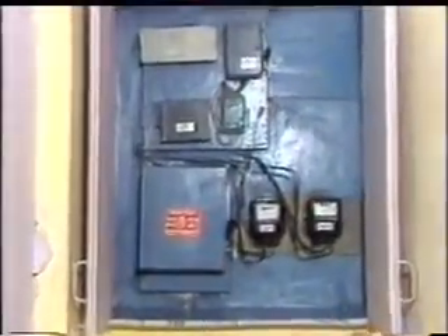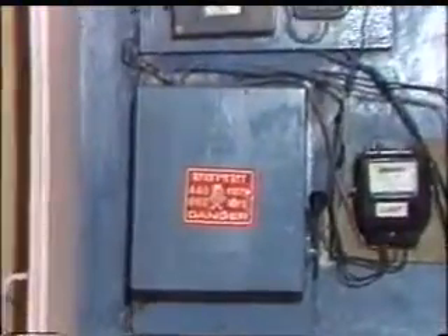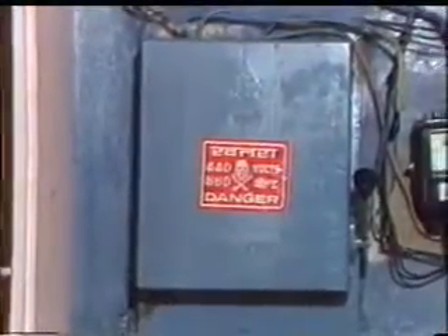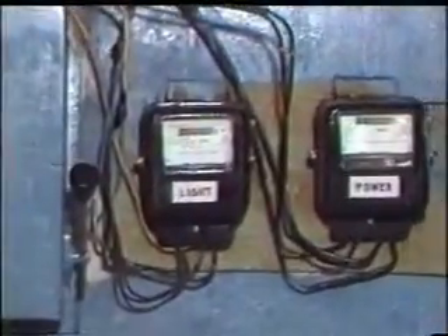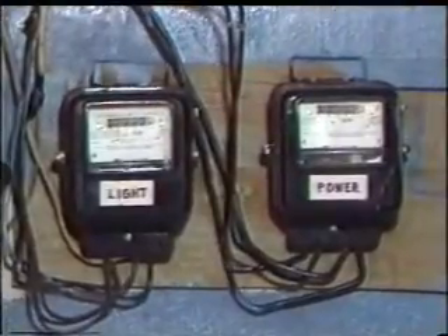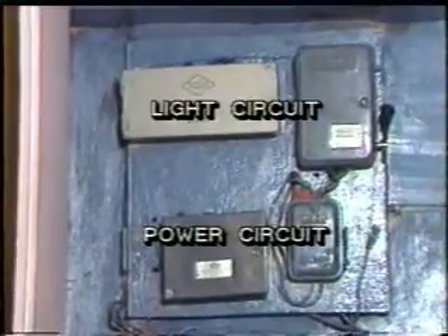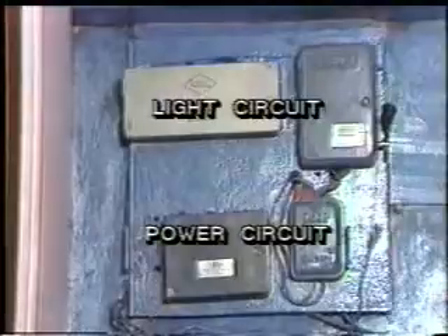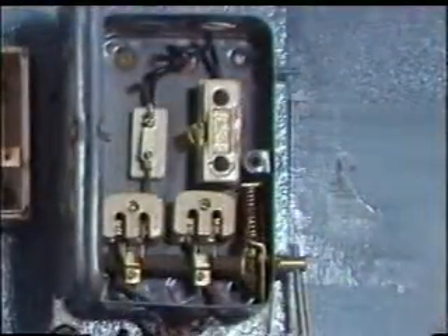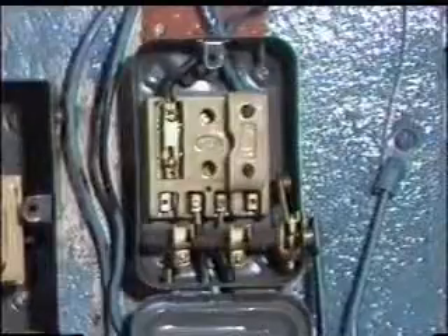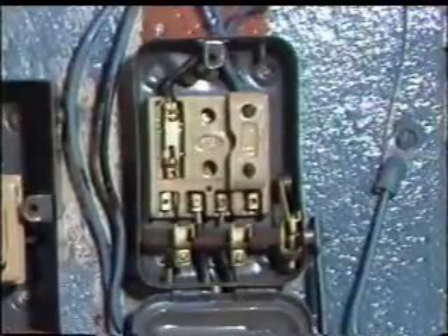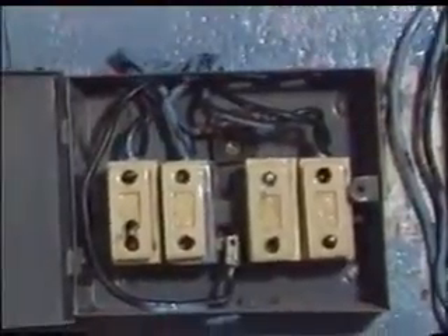In a domestic wiring installation, two types of circuits are drawn. One is called light circuit and the other power circuit. Light circuit caters to fans and lighting load, whereas power circuit caters to 15 ampere socket outlet loads. This is done to achieve reliability and economy. This is the main switch and distribution box for light circuits. Similarly, there is a separate main switch and a distribution box for power circuits.